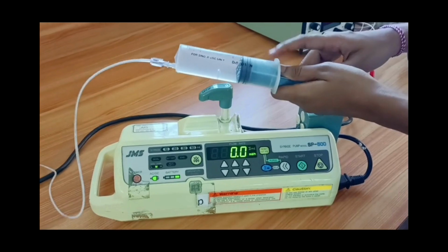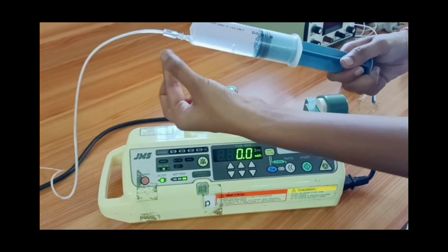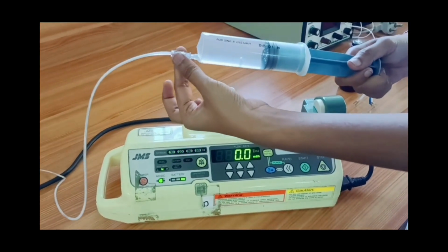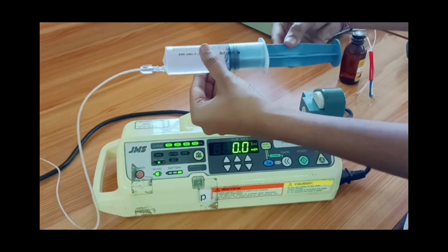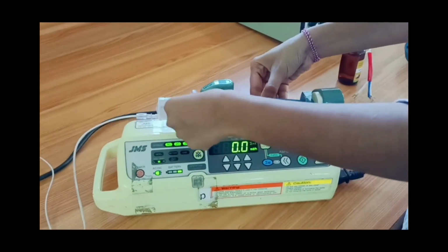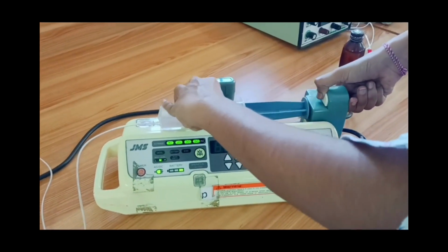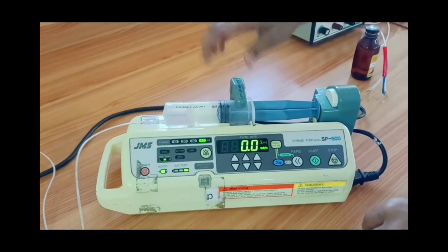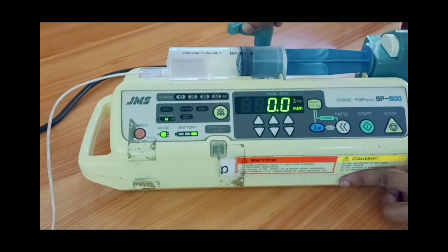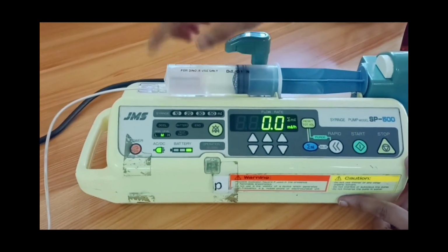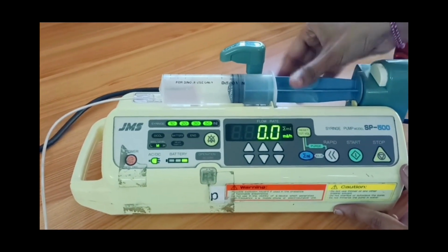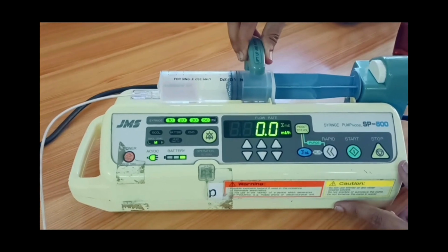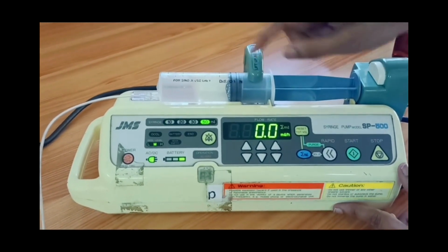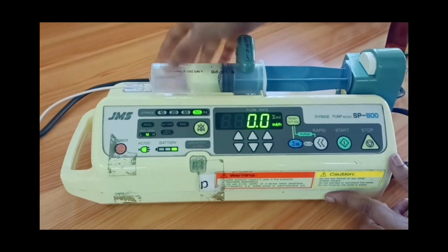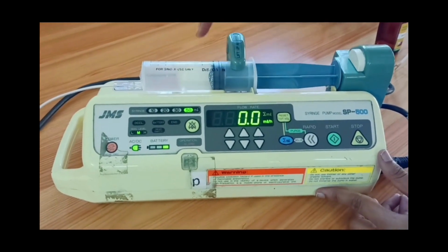Now I have taken the fluid into the syringe pump and connected the intravenous tubing to the other end of the syringe. Now I am placing this syringe in the holder. See, before these were blinking because I had not set it properly. After putting this barrel detector down, this is set to 50, indicating that this syringe pump can hold 50 ml of fluid.